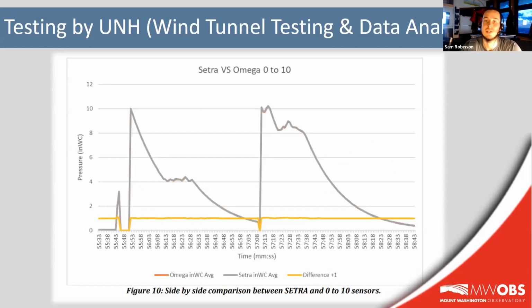So to verify that the reference pitot cetra sensor was well calibrated, they tested it with that same calibration tool that we used for that very first initial test on pitot 22 sensors. And only a minimal difference was found between the outputs of the reference pitot and pitot 22, which can be seen in this figure here, figure 10. The data plotted here is pressure reading over the course of that test time. The data between the two is actually so close, it's hard to tell even where they differ. If you look at 56 seconds and 56.18 and 57.38, you can slightly see a little bit of red underneath the gray, but it's really hard to tell where they differ. And since this reference pressure sensor was not found to be faulty, then some further investigation focused on the physical setup in the wind tunnel.